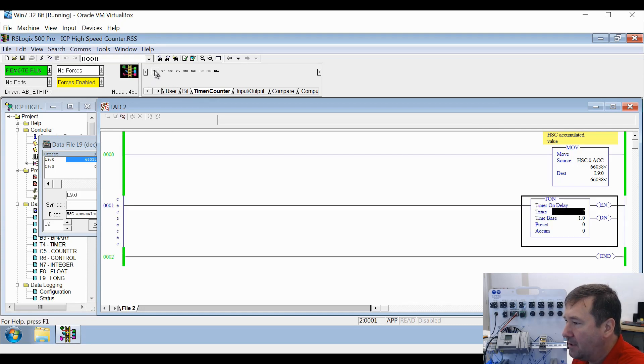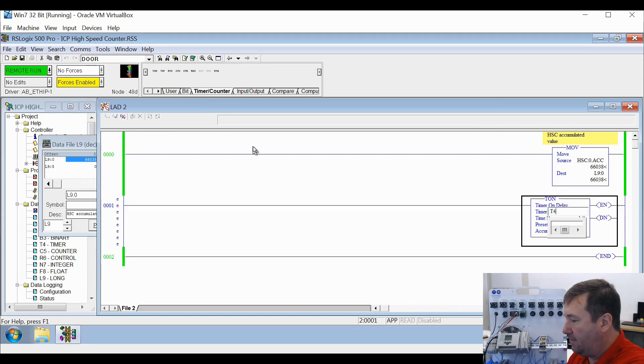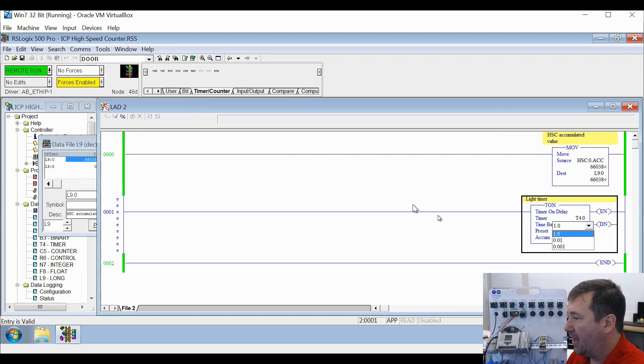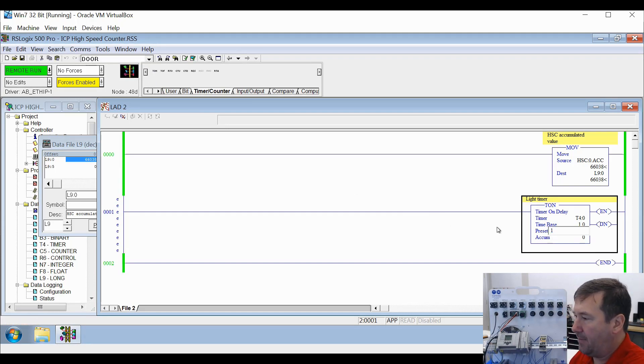So the first thing I'm going to do is add a timer. We'll get to our timer tab and TON - we're going to use T4 colon zero. We're just going to use a one second time base and a preset of one. And that's it for the first rung. There is no input instruction - there's nothing wrong with that either.